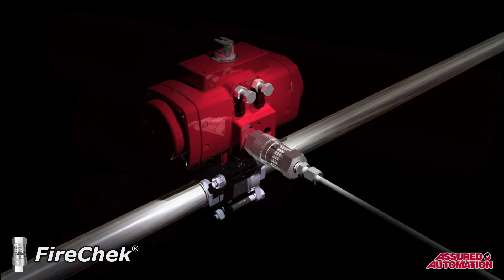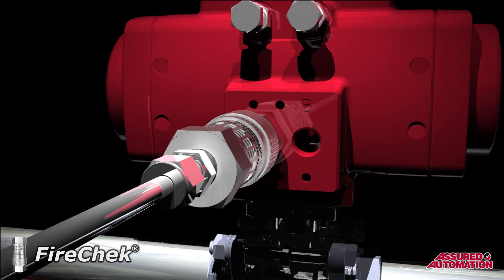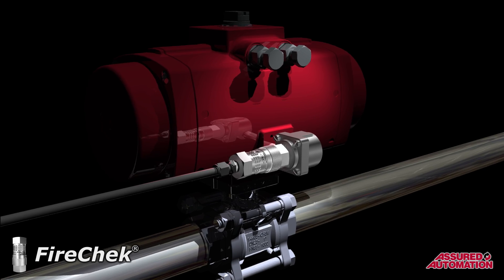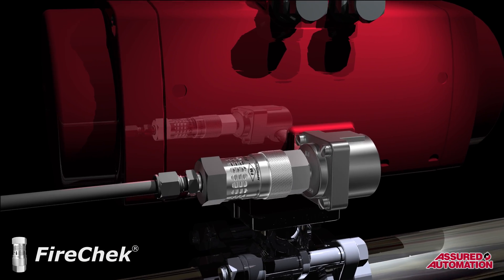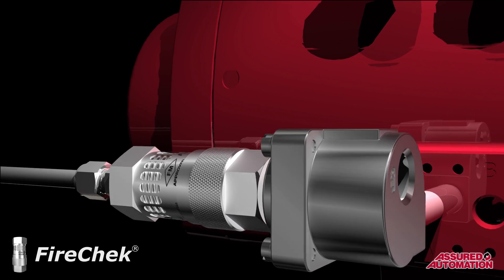The FireChek valve by itself is suited for use on smaller actuators, typically those found on valves up to 4 inches in size. When larger valves require emergency thermal shutoff operation, the FireChek valve with quick exhaust drastically increases the exhaust speed of the pneumatic actuator, providing a faster return to fail-safe.